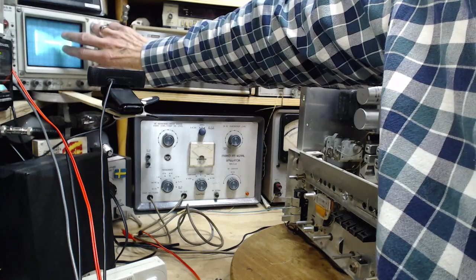So we set this back to sweep. The 60 cycle sweep here, we set this to utilize it. The 60 cycles is now doing this. Now there's no blanking in this device at all, so it's sweeping back and forth. So it's really painting this weird image twice, and probably painting it with a little bit of phase shift. There's a phase shift between the two versions of it.